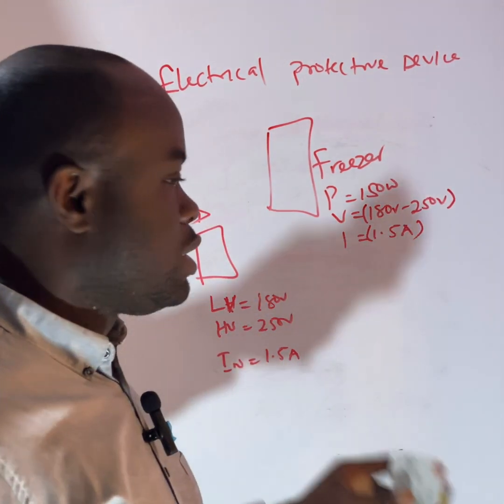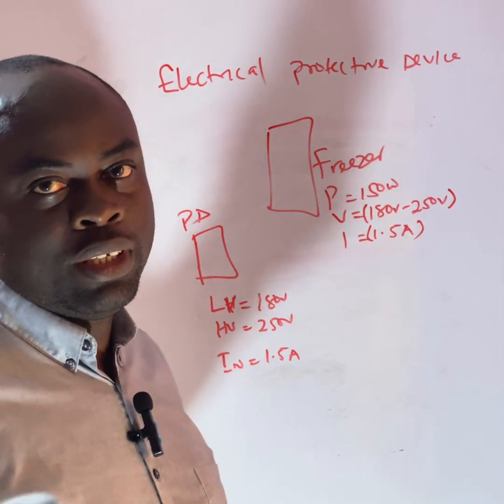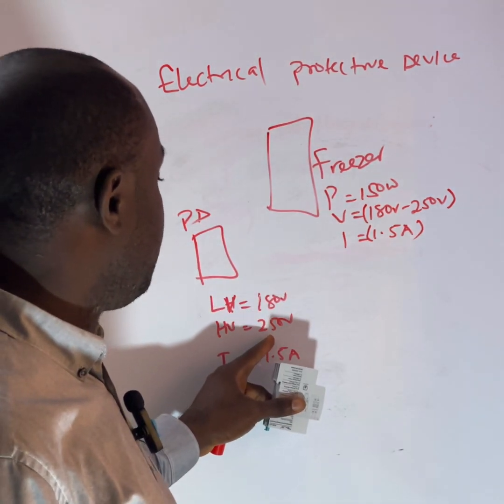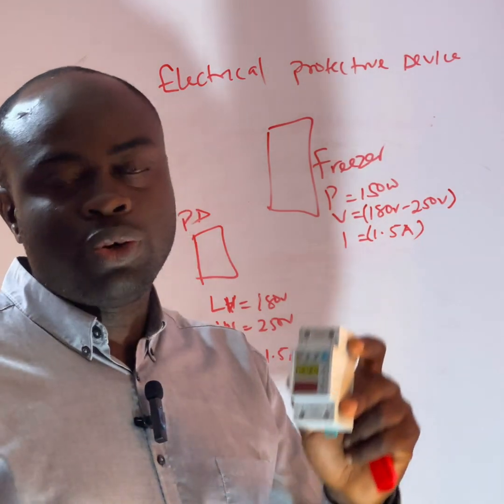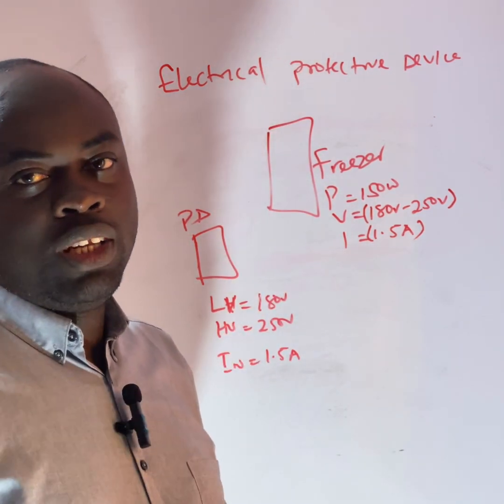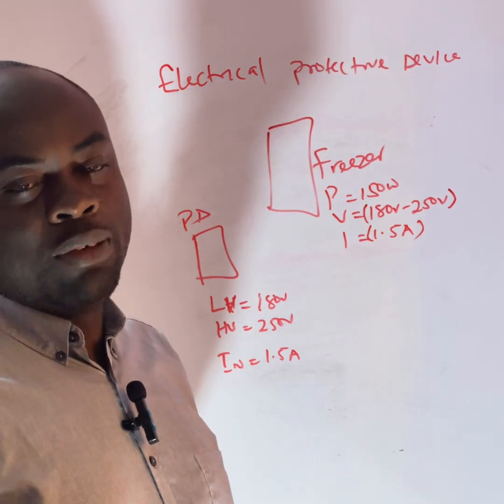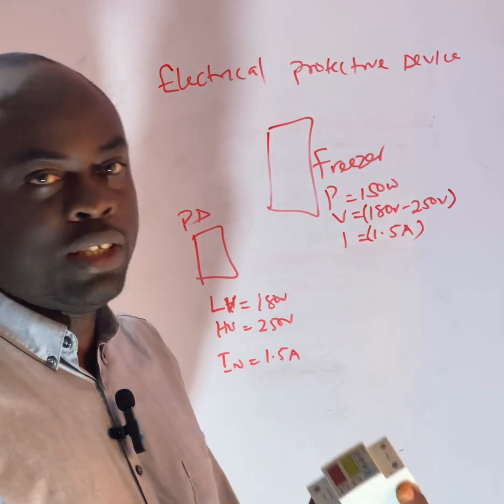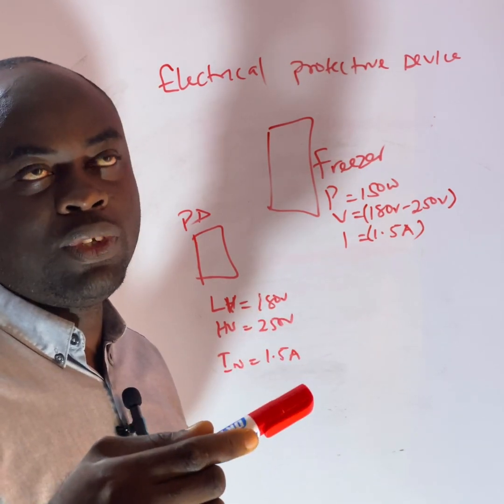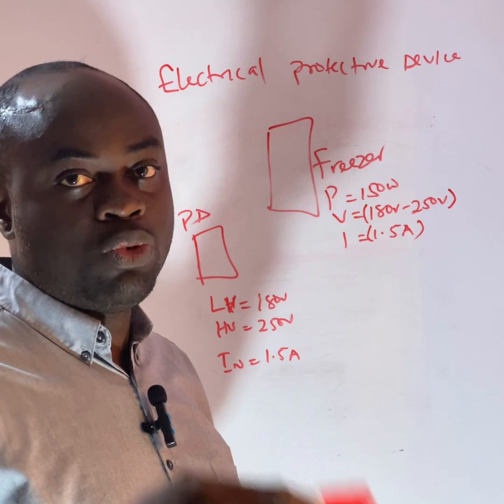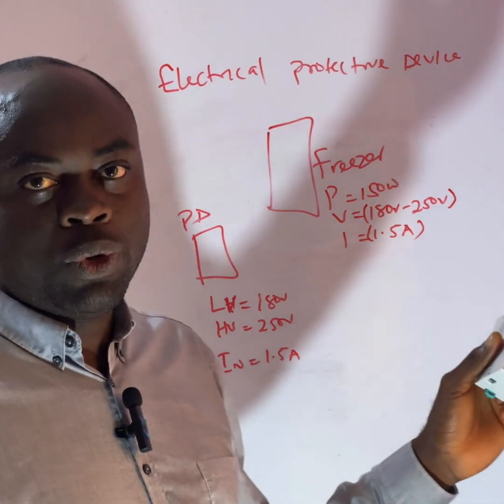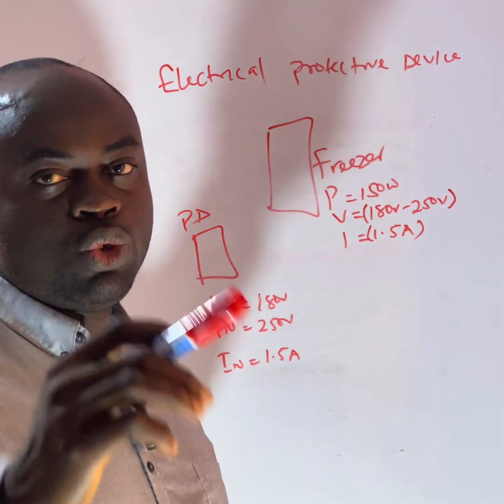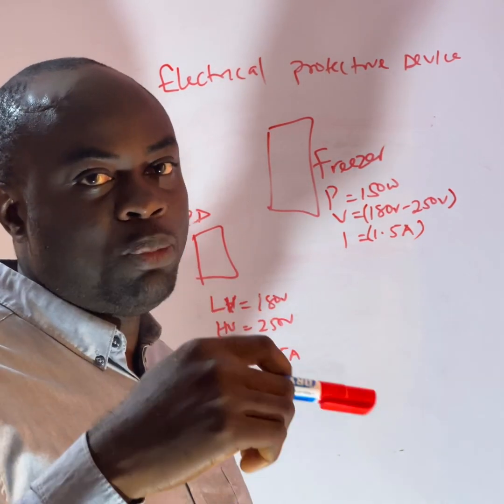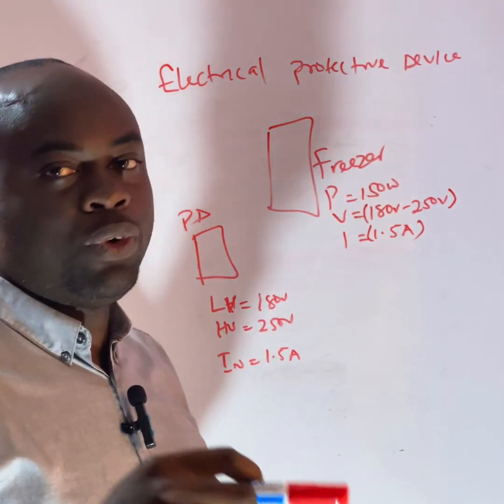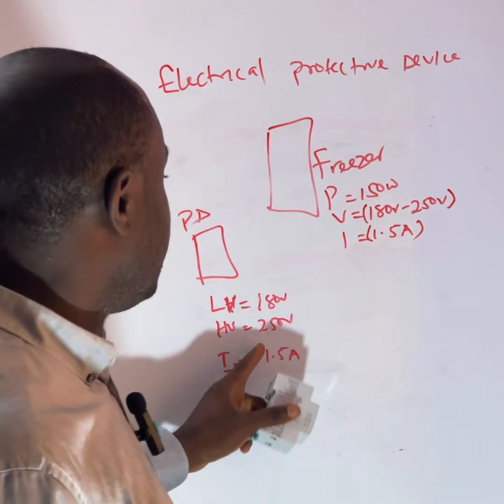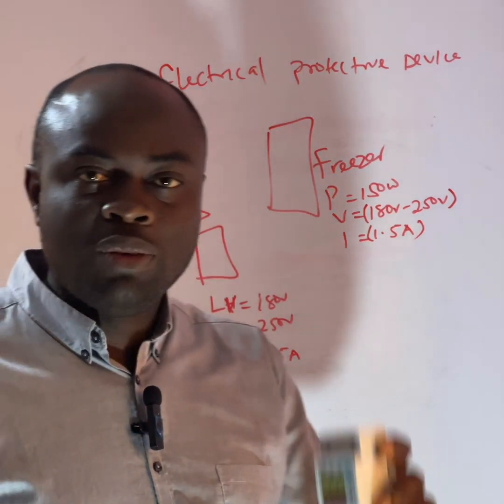So another beauty of it is this: the device has a delay timer, meaning if the voltage is above 250 volts and the device cuts off the voltage, your freezer will be off. Now, will it not be off permanently? No. After the time you have set with the timer in it, it will monitor the voltage. Oh, has this voltage dropped below 250? If it has dropped, it will come on. Once it comes on, the equipment can be working. But if it monitors it and the voltage is above it, it will try to come on. Once it comes on and detects that the voltage is above 250 volts, it will shut off again and wait for the time you have set to delay before it comes on. The same applies to your low voltage and your current. That's one beauty about this device.